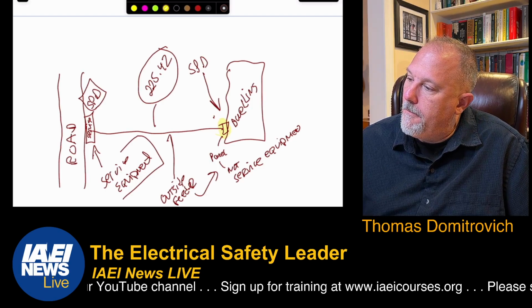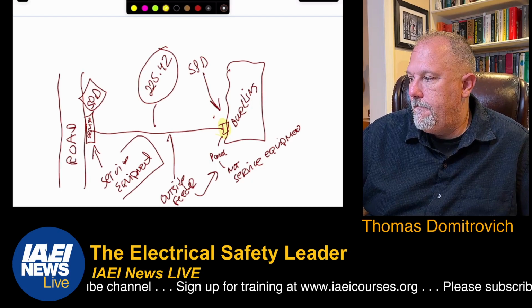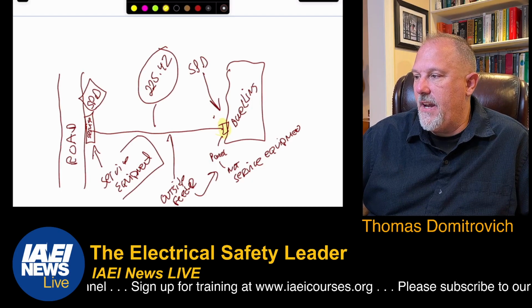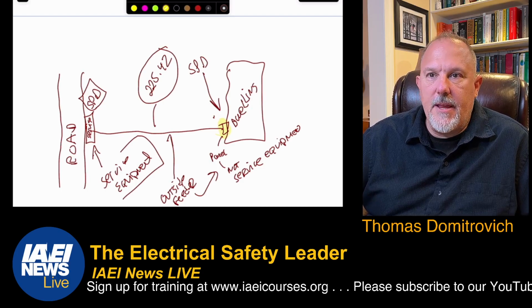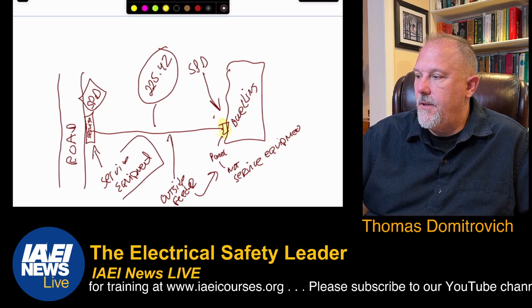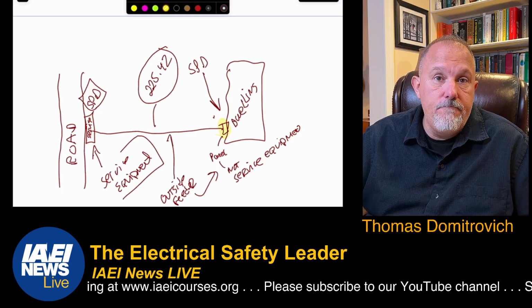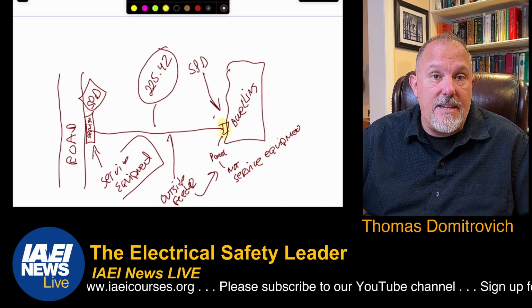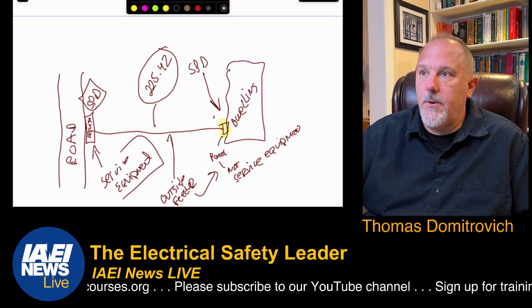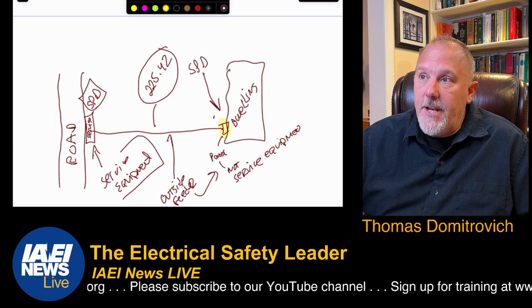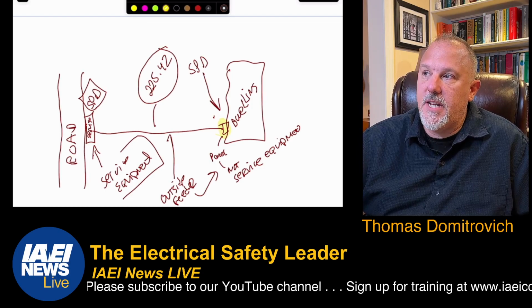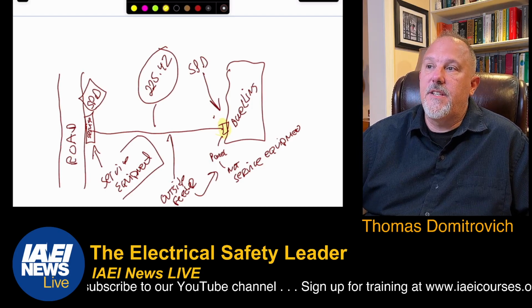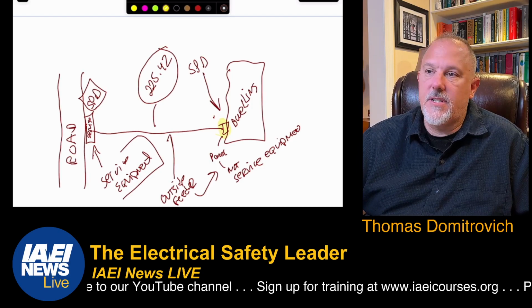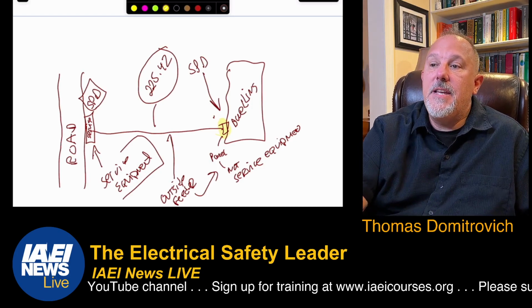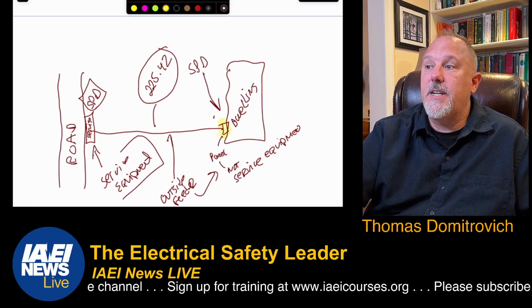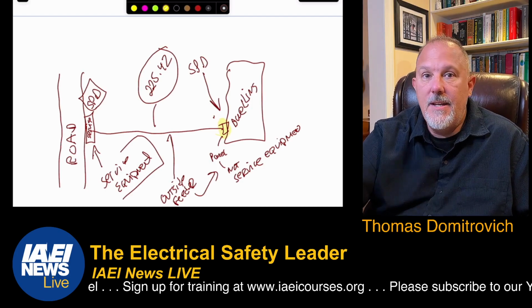So for the outside feeder in 225, we put the same language in 215. We don't really need the requirements in 225.42 because it's in 215.18 for feeders, any feeder, indoor or outdoor. And it has the same language. Where a feeder supplies any of the following, a surge protective device shall be installed when it supplies dwelling units, dormitory units, the same four locations. And it says the SPD shall be installed in or adjacent to the distribution equipment connected to the load side of the feeder.